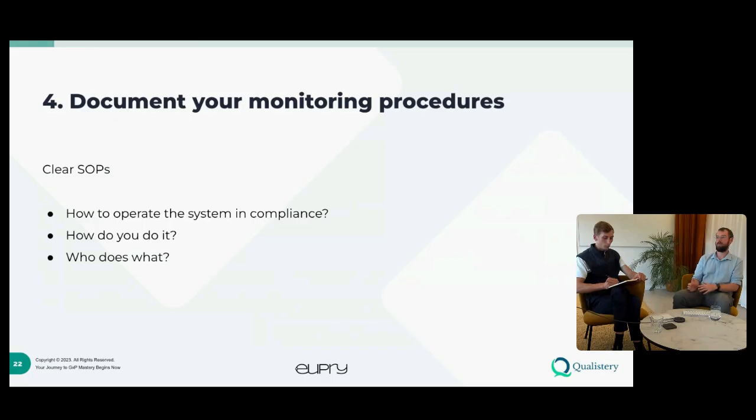So again, back to one of the first slides, you can never have a system that is fully 21 CFR Part 11 compliant by itself. You need to operate it compliantly. And often auditors will require you to have SOPs that instruct its users exactly on how to do it. How do you use the system and who does what? Part 11 also has some very tight specifications that you need to have an authorized way of performing certain actions.